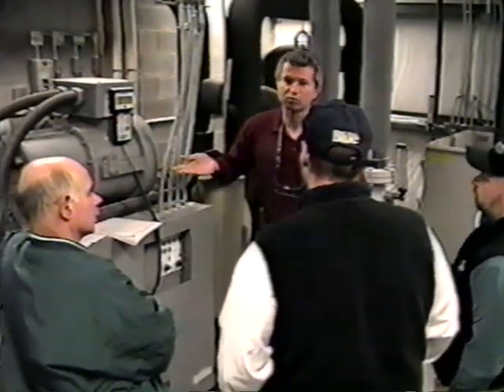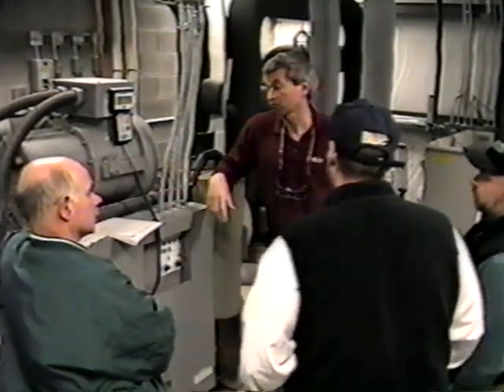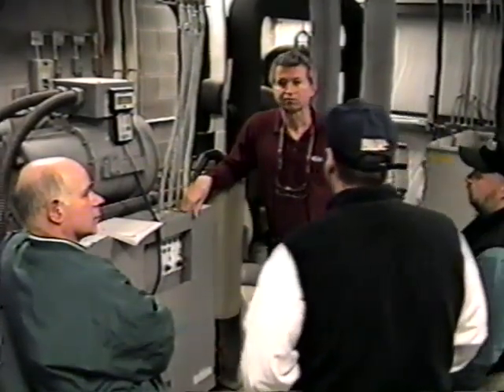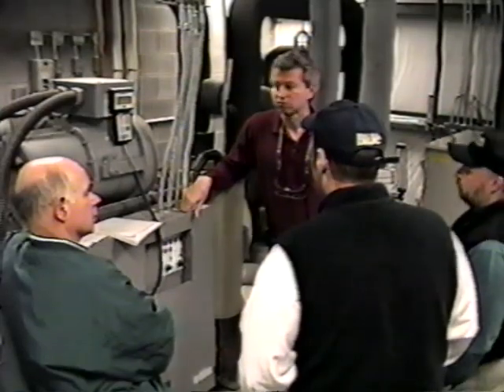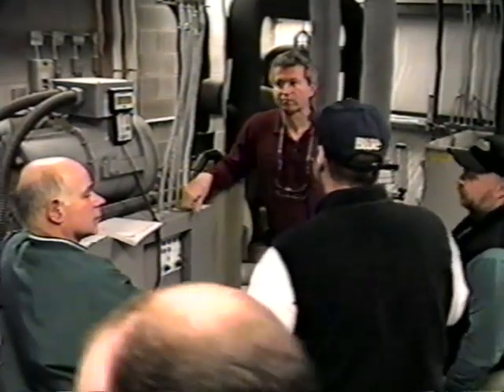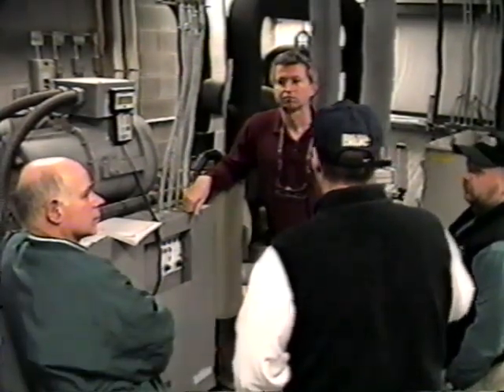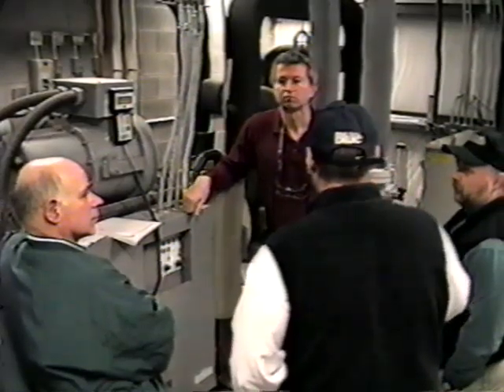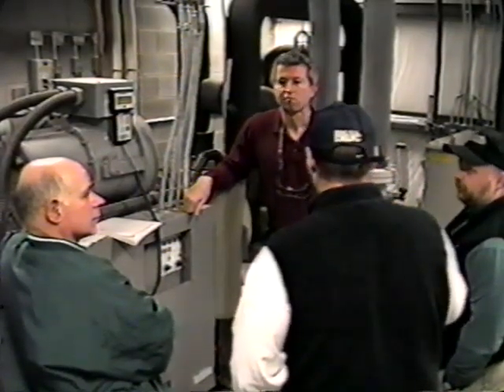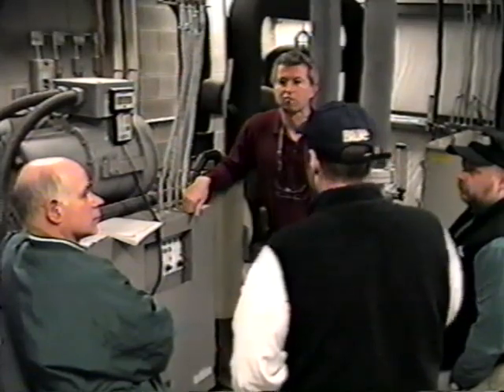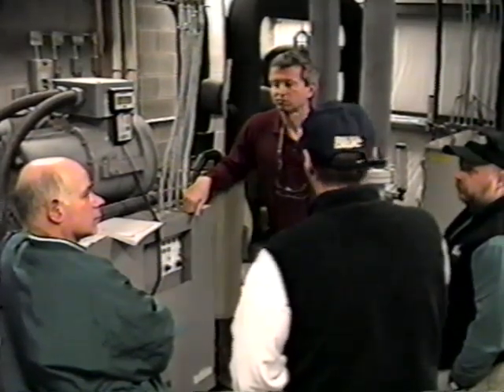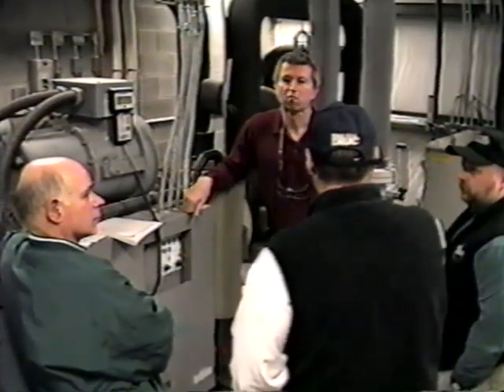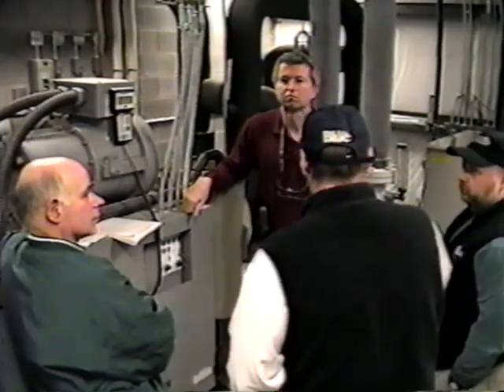I guess you switch to low speed on your pump. Right, that's what it is, it just winds the pump down to low speed. Now, over there, all we take is suction, discharge, head pressure, and hours, basically hours of running time. Like I said, compressor 1 is the main compressor now, so that's the only one we're going to run.